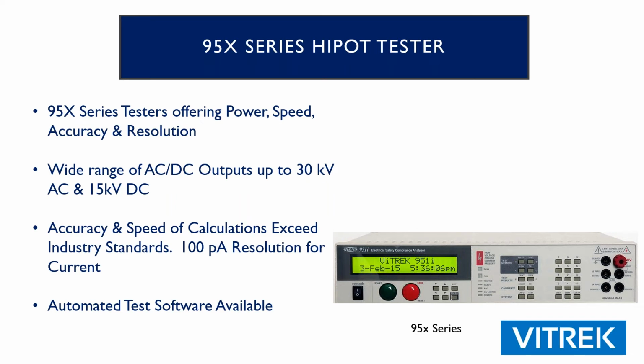All right, so the main instrument that's really the brains behind the test and measurement side with these printed circuit board test systems is going to be the 95X HIPOT tester. This is the source and measurement unit. It's got a wide range of outputs from as low as about 25 volts up to 30 kV. Really the sweet spot for this thing is the 5 to 10 kV high end kind of voltage requirements. We're looking at 100 picoamps of resolution on the current side, so we're able to measure very, very low levels of current, which translates to very high levels of insulation resistance in your products.